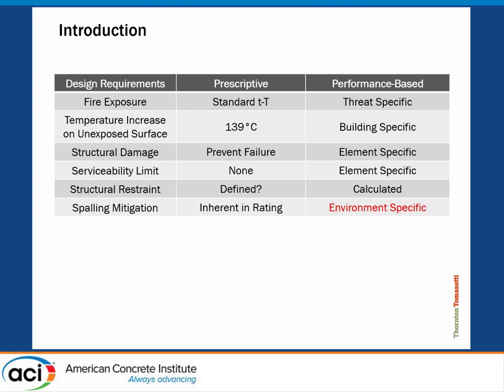When we go to a performance-based world, everything becomes specific to the problem at hand. Your fire exposure is threat-specific: bridge fire, deck fire, building fire, industrial-type fire. Temperature increase may not even matter — we may be more concerned with structural load-carrying capability. What damage can you incur? Some buildings allow very little damage due to their importance; others could tolerate six inches of deflection. All response limits become specific to the element. The restraint can actually be calculated — let's model the beam-column connection. For concrete, most everything's monolithic; we can put that into our models.